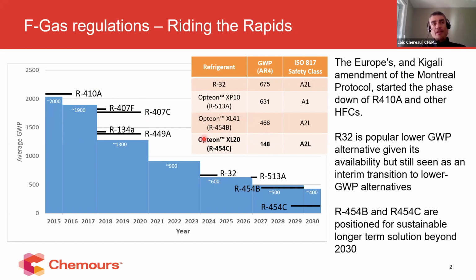If let's say the 407C would be the reference, the immediate near drop-in solution that could also be considered is the 454C, because of, again, the performance that can be achieved, even though there will always be a redesign to be taken into the heat pump to make sure the efficiency can be as good as it was from the initial HFC refrigerant.